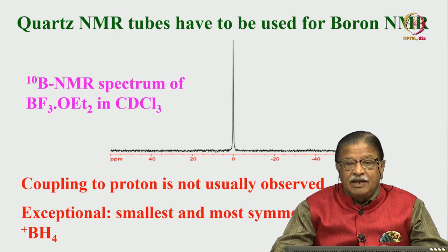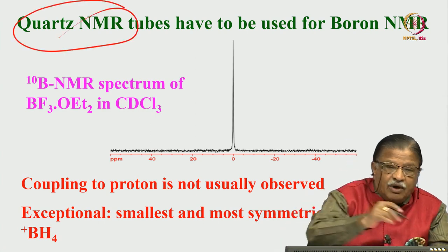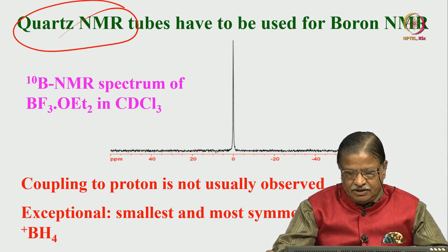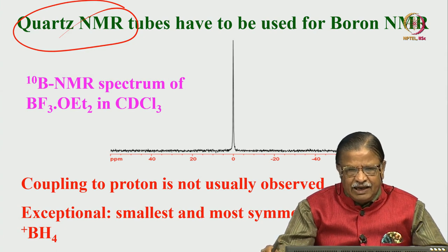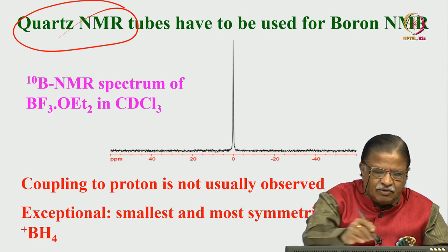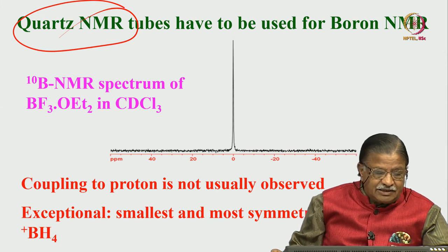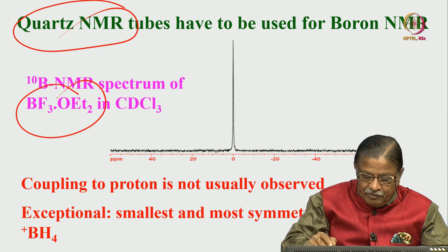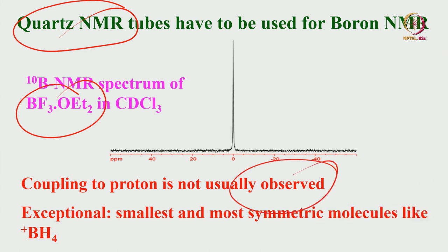One important practical note: if you want to do boron NMR, you must use quartz NMR tubes. Do not use normal tubes, because they are made of borosilicate glass and you will get a signal from the NMR tube itself. This is a caution — when doing boron NMR, always use quartz NMR tubes. For BF3·OEt2, coupling to proton is not usually observed. Only in exceptional cases like the BH4 molecule can you see boron-proton coupling.